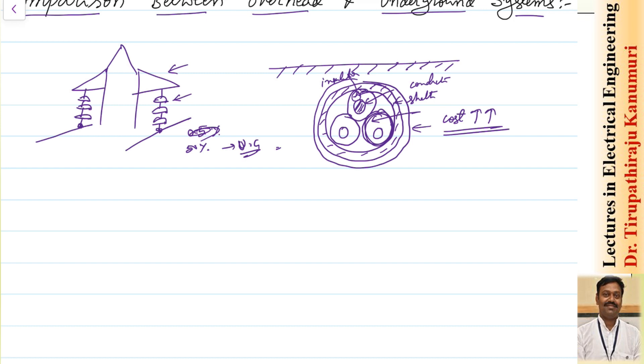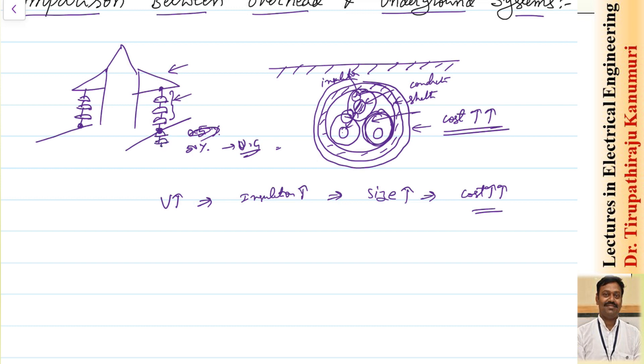Coming to working voltage: in underground cable, the voltage is between two conductors, which is the line voltage. In overhead lines, the voltage is between the conductor and the tower, which is the phase voltage. As voltage increases, the thickness of insulation required increases, so the cable size and cost increase drastically. Whereas in overhead lines we just add more insulators and increase tower height slightly, so the extra cost for higher voltage is much less.